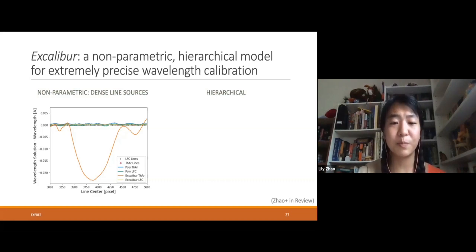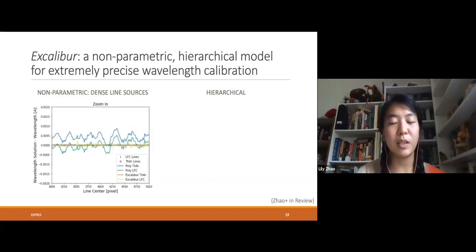And so you don't really have the amount of information you need to constrain the wavelength solution at all points in the detector. But if you zoom in, you'll see that the polynomial fit, regardless of whether you're using the thorium-argon or the LFCs, has essentially the same shape in the residuals. And so you're not really using any of the information you get out of the denser LFC lines. But using a non-parametric model, this yellow line, you get the smallest residuals of any of the models.